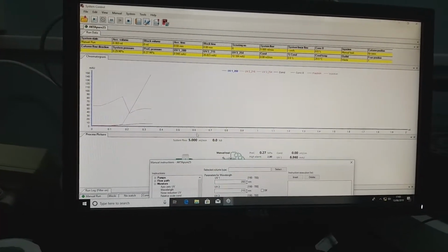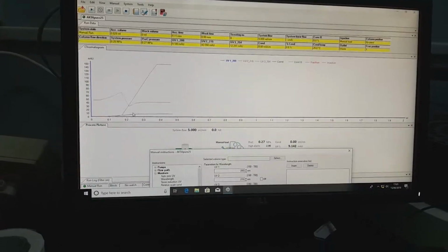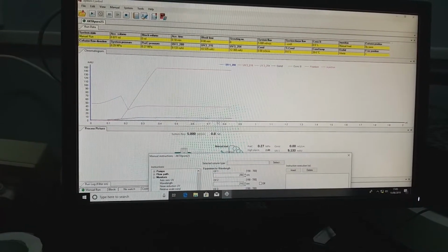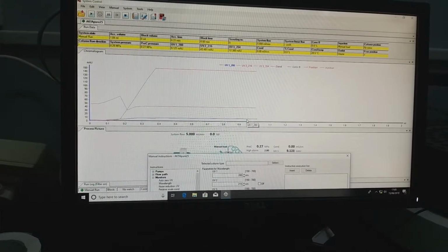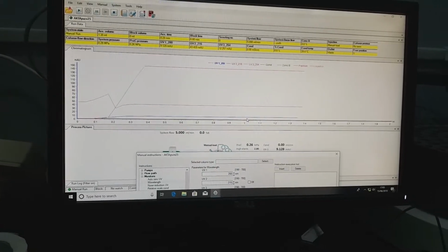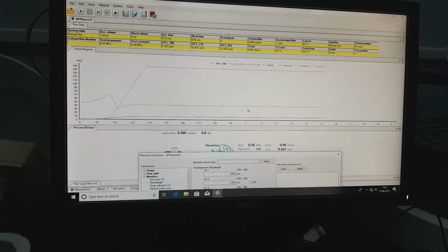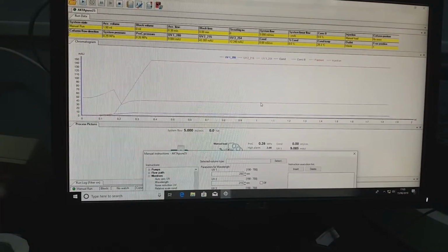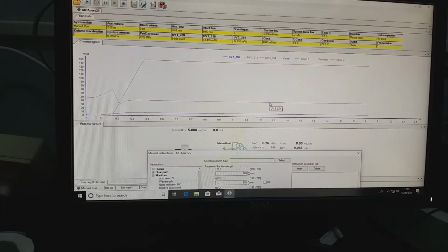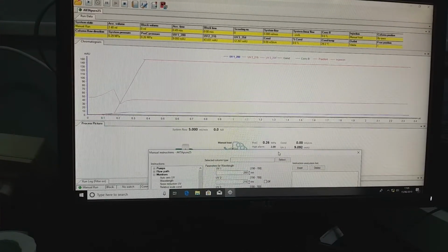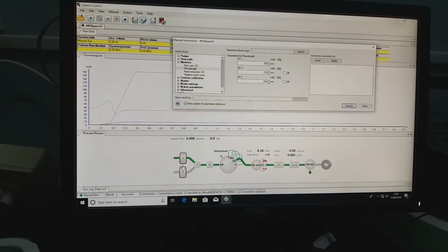You can see the green path is highlighted and also chromatograms appearing in the chromatogram area. So it will give 3 different chromatograms. One corresponding to blue, that is 280 nanometer for tryptophan tyrosine fluorescence. Second one is 254 nanometer for RNA or DNA related, and third one is 215 for peptide.